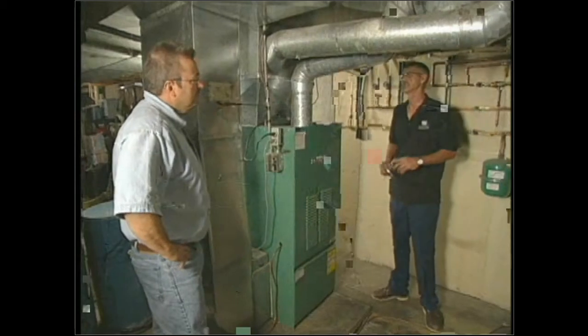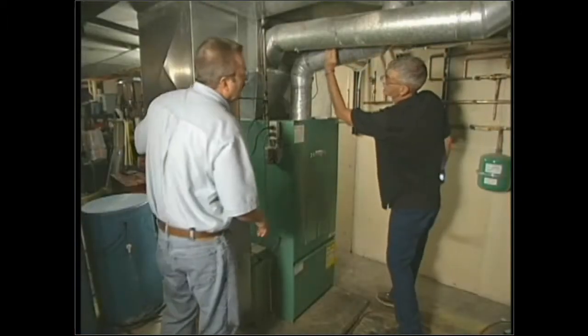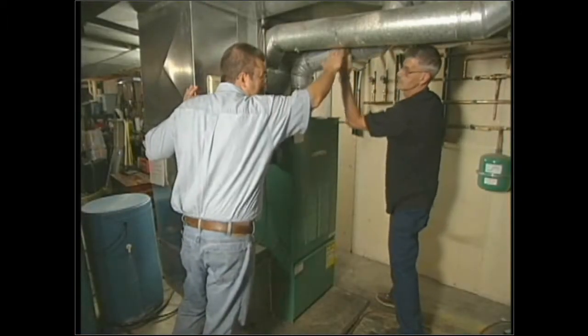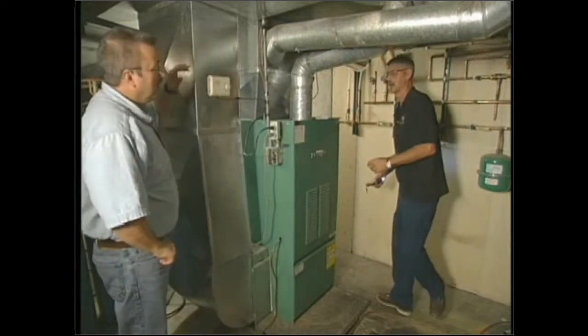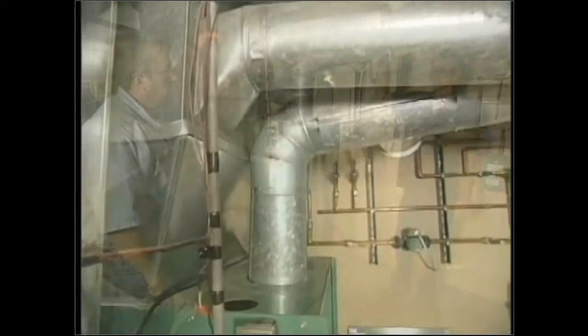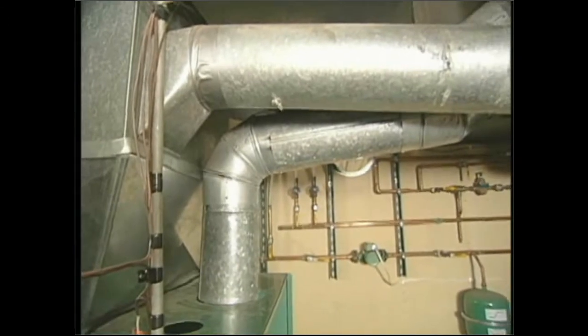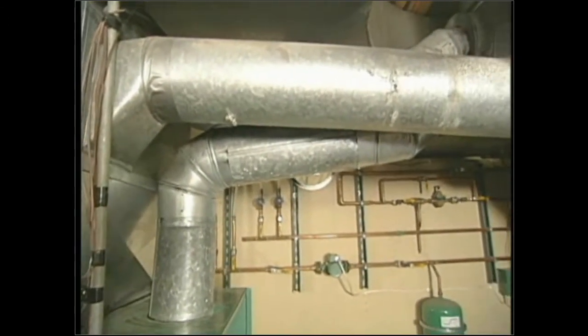Another thing I'll do is I'll take my flashlight and I'll look inside of the flue. And what I'm looking for is buildup of debris, rust, and soot. And over time, some of these units can really get full. I see them filled up to right about halfway, right about up into here. That much soot can be found inside there? Yep. So now what you've done is you've taken what would be a 6-inch flue and reduced it down to a 3-inch, which makes it harder to draft. If that is the case, then we'd have to take this apart and clean it.